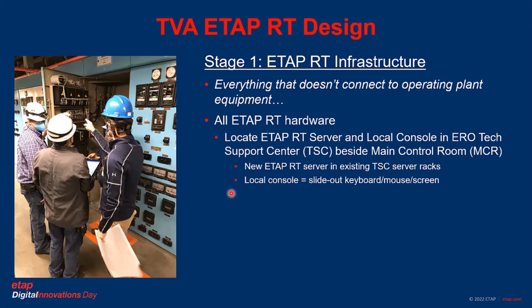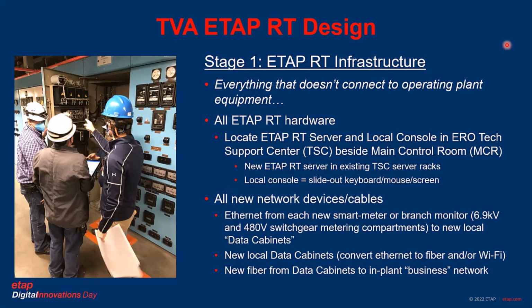We're going to locate the ETAP RT server and local console in our ERO Tech Support Center, which is near the main control room. As I said, we'll have a new ETAP RT server, and we're going to locate that in some existing TSC server racks. And we'll have a local console, the typical kind with a slide-out keyboard, mouse, and screen. This also includes all new network devices and cables. So Ethernet from each new smart meter or branch monitor, and everything that needs to connect to the local data cabinets. We'll also have new local data cabinets, which will convert the Ethernet to either fiber or Wi-Fi, as I said, and then we'll have some new fiber from the data cabinets to our in-plant business network.